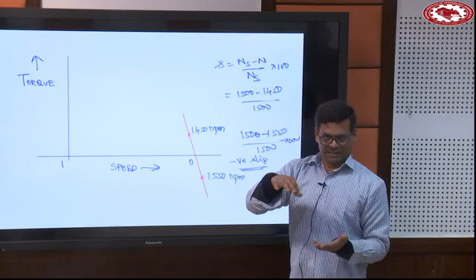Okay. So now, can you tell me the speed range of the induction motor? Speed range of the induction motor is just 50 rpm. At no load, it is a 10 rpm difference, the speed difference between the magnetic field and the speed of the rotor, 1490 rpm, when load is not connected. When the full load is connected, full load in the sense that the current in the stator winding is the rated current. If it is designed for 5 ampere, it will be 5 ampere. You should not load it beyond.